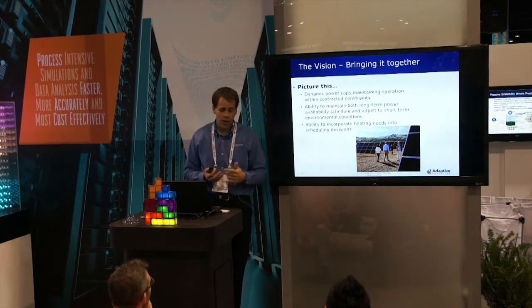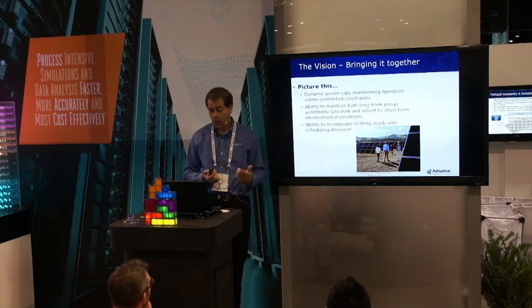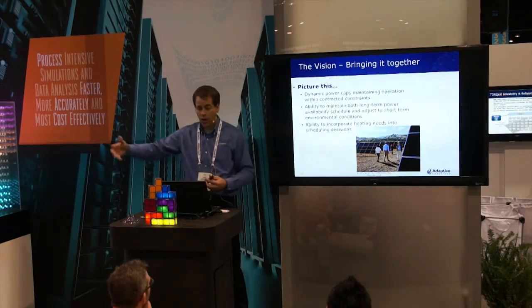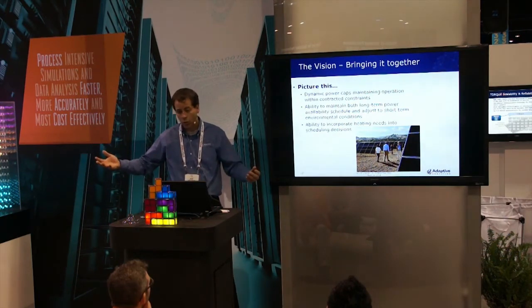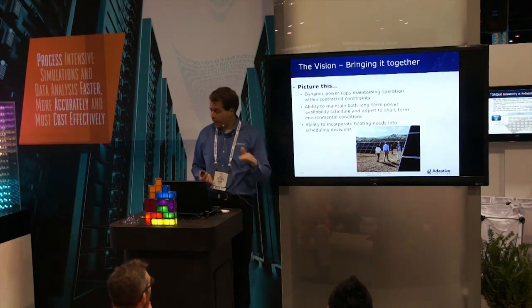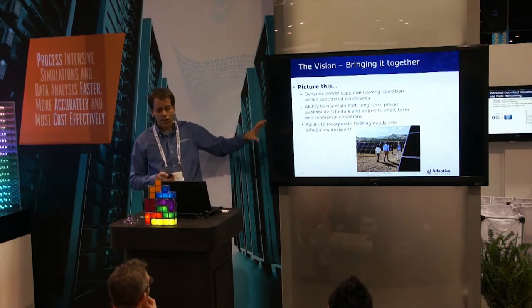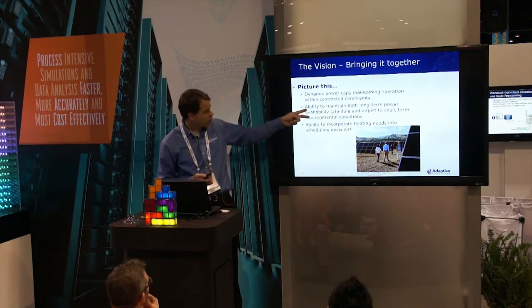You're also going to have other types of unexpected situations. The power company will call you up and do this on-demand power thing where they say, you know what, I need to yank another megawatt of power from you guys because I have a surge over here, or it's getting too hot out there, air conditioning is going up, I need you to increase or reduce your power. And so you have to do dynamic modifications to your power budget that you may only get an hour or 2 hours of notice on. So the scheduler has to be aware of these dynamically changing power budgets and power caps. So both this is the long-term and short-term.